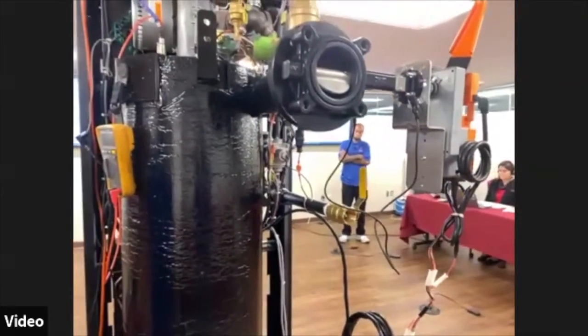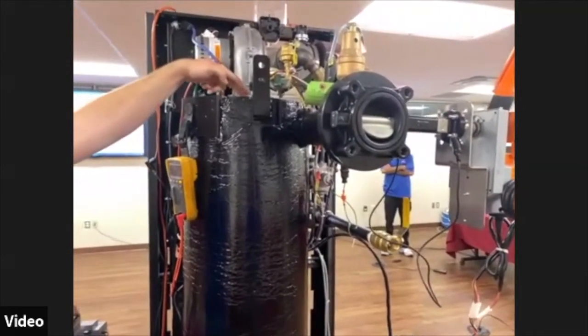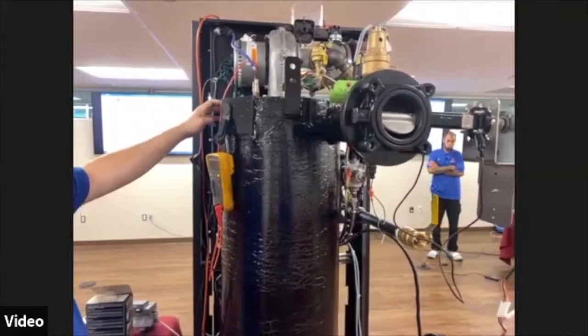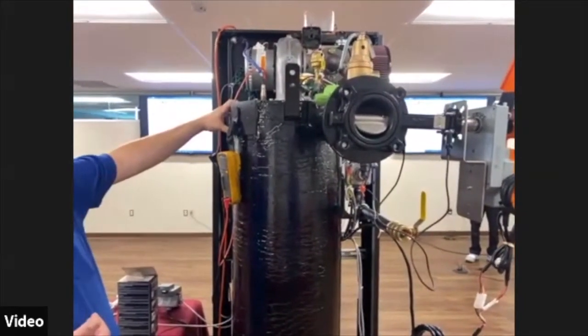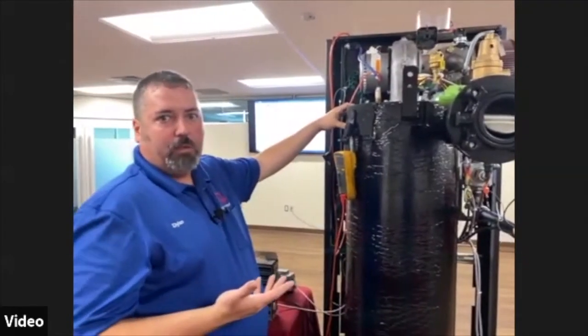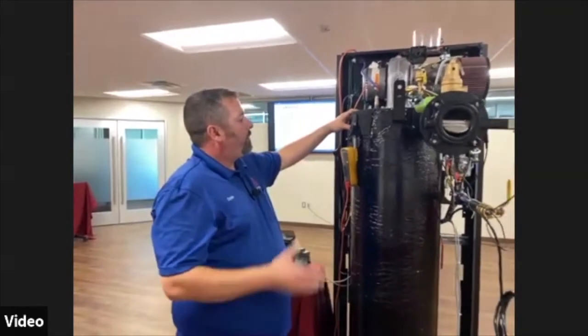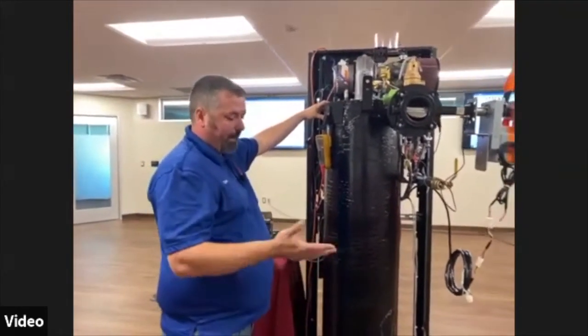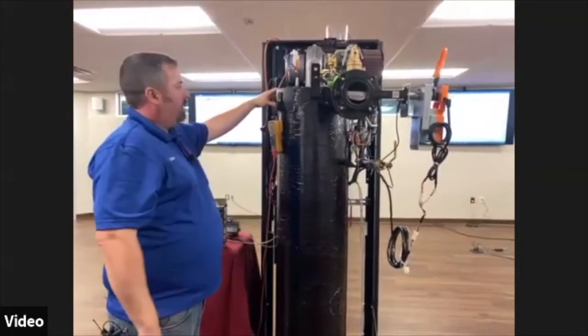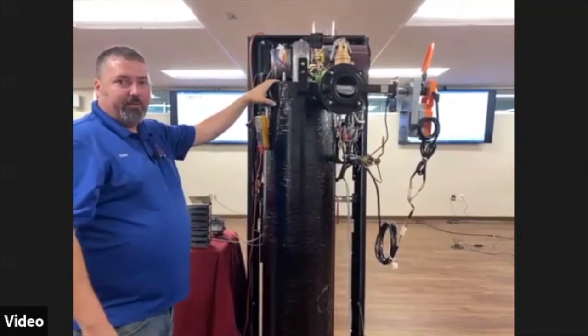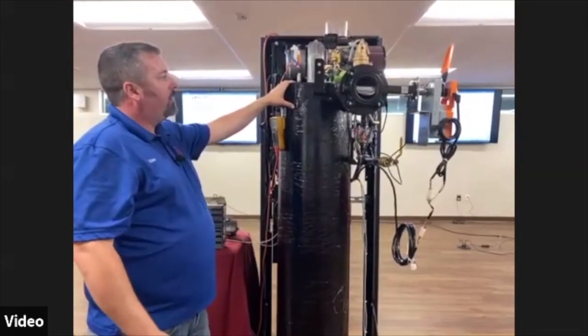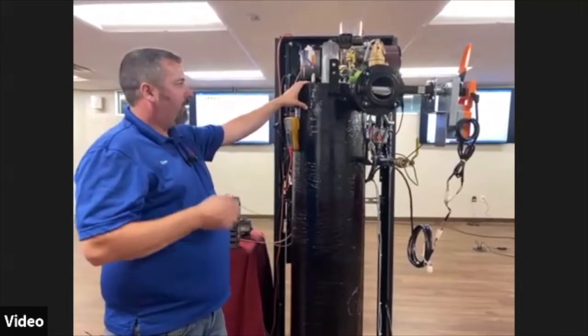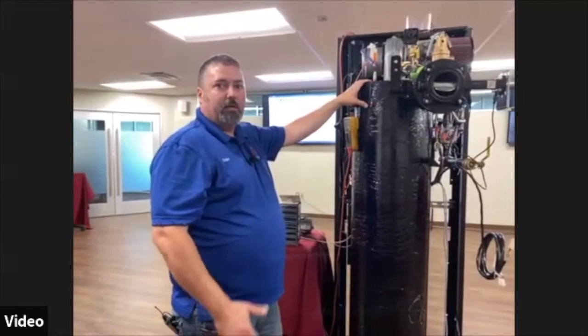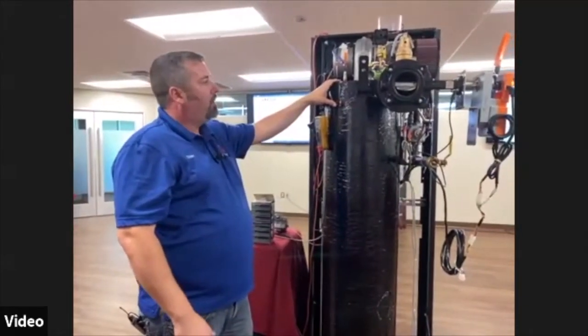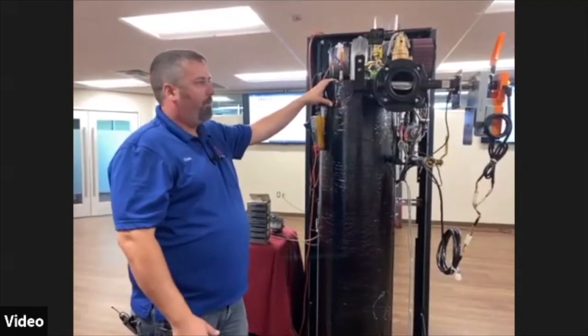As for the annual maintenance, Aerco sells an annual maintenance kit, which includes a replacement flame sensor, a replacement igniter, and an O-ring for the condensate trap. Annually, what you'd want to do is obviously clean or replace those depending on the condition of them. Clean your trap again, semi-annually and annually, obviously. Clean the trap and neutralizer. And then you'd also want to do all your safety device testing and CSD1 testing, especially here in Michigan. That's a good time to go through and do all your CSD1 testing. You should adjust calibration at least once a year to make sure your boiler is running at proper efficiency. That'll keep it running and keep it condensing properly and give you a long life on your boiler.